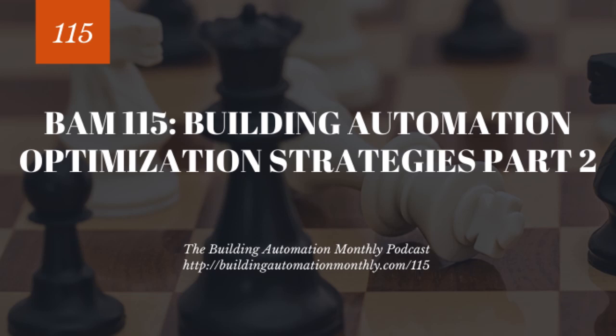If you don't do those two things, I know I'm hitting you over the head with this again and again, but this is so important. I've done so many service calls where the issue was simply an inaccurate sensor, a sensor that either wasn't properly wired up, or it wasn't properly calibrated, or there wasn't a proper offset, or there was a device that wasn't controlling properly, wasn't properly mounted, wasn't properly installed. And because of these two issues, no matter what optimization strategy you implement, you're not going to achieve your goals. So you need to knock those two things out first.